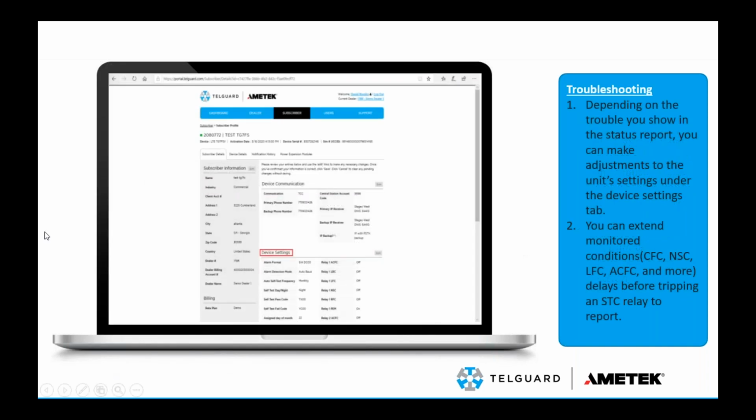Now, troubleshooting. Let's say you have a TG-7FS at a site, and every day or every other day, or maybe a couple of times a day, they have construction going on at the site, because that's a very real scenario. These guys are overwhelming the circuit board, the breaker box, and are tripping some of the breakers. So the panel keeps powering down, and in this case, an AC failure condition keeps happening on our TG-7FS.